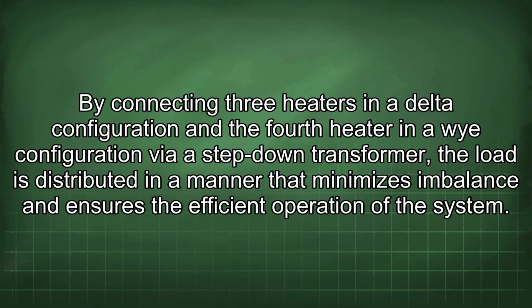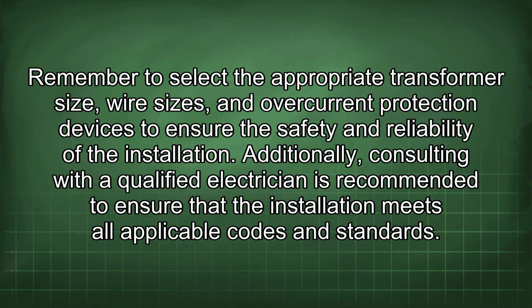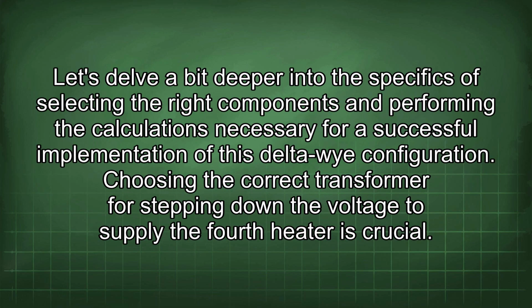By connecting three heaters in a Delta configuration and the fourth heater in a Y configuration via a step-down transformer, the load is distributed in a manner that minimizes imbalance and ensures the efficient operation of the system. Remember to select the appropriate transformer size, wire sizes, and overcurrent protection devices to ensure the safety and reliability of the installation. Additionally, consulting with a qualified electrician is recommended to ensure that the installation meets all applicable codes and standards. Let's delve a bit deeper into the specifics of selecting the right components and performing the calculations necessary for a successful implementation of this Delta-Wye configuration.